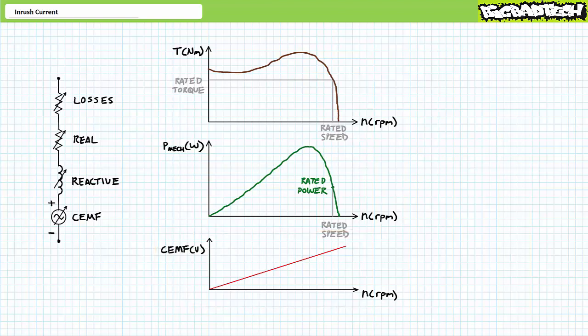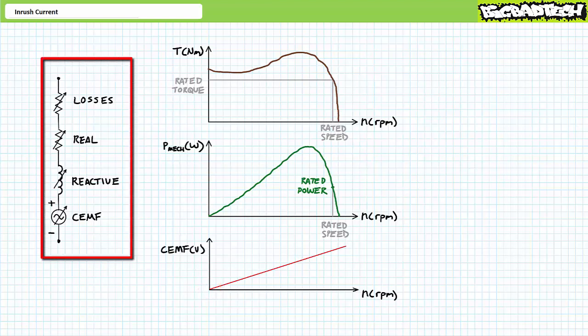This effect explains inrush — or more appropriately, it is a lack of this effect that explains inrush. A motor at rest is not producing counter-electromotive force, and upon closure of a full-voltage starter, the winding experiences full voltage. Consider this simplified model of a squirrel cage induction motor winding consisting of several components: a small variable resistance representing losses inherent in a motor's operation — resistance losses, core losses, sound losses, winding losses, bearing losses — and a second variable resistor representing the real power consumed by the winding.